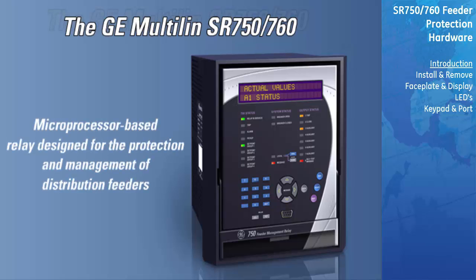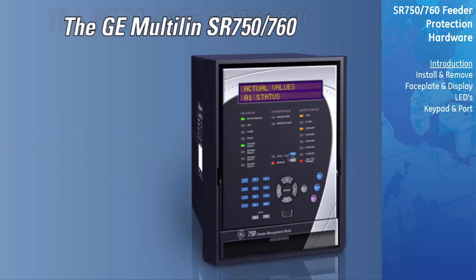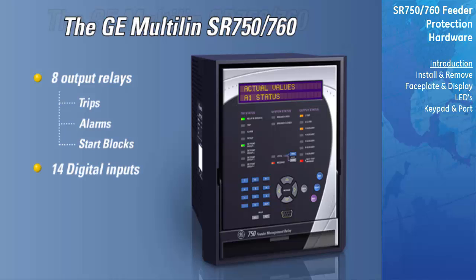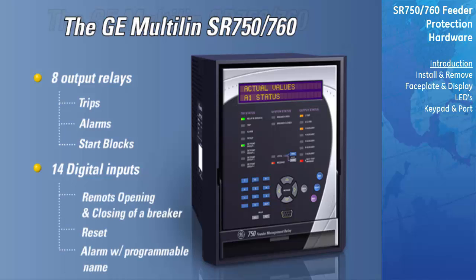SR-750-760 feeder management relays are microprocessor-based relays designed for the protection and management of distribution feeders. They are equipped with 8 output relays for trips, alarms, and start blocks. 14 digital inputs may be configured for different functions, such as remote opening and closing of the breaker, reset, or alarm with a programmable name.